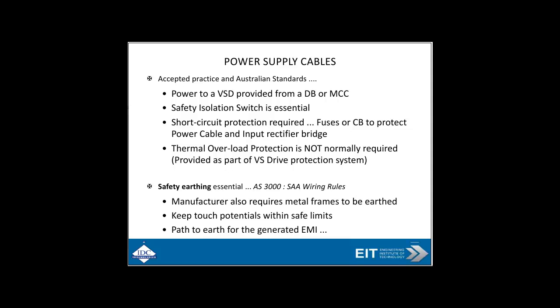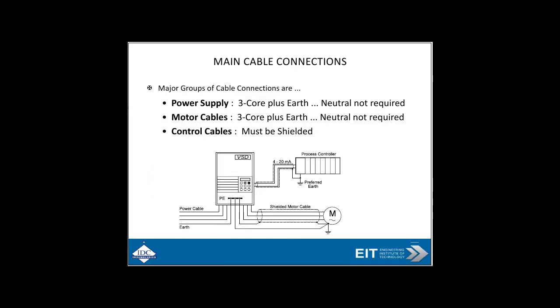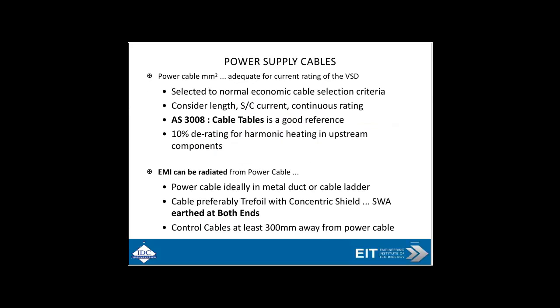Power supply cables: use accepted practice per Australian standards. Safety earthing is really important, as per other wiring rules. Here's an example of the main cable connections: power supply is three-core plus earth — or 'ground' as the Americans call it — neutral not required. Motor cables are three-core plus earth, neutral not required. Control cables must be shielded because there is a ferocious amount of harmonics due to the pulse-width modulation square wave output.